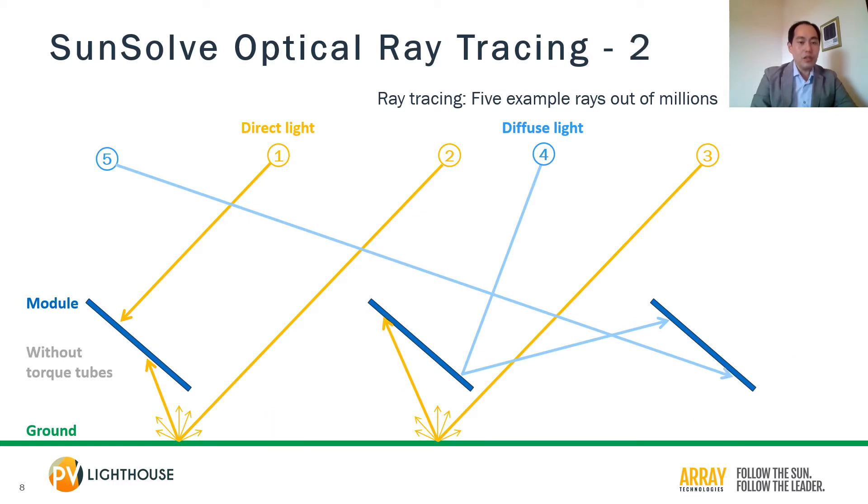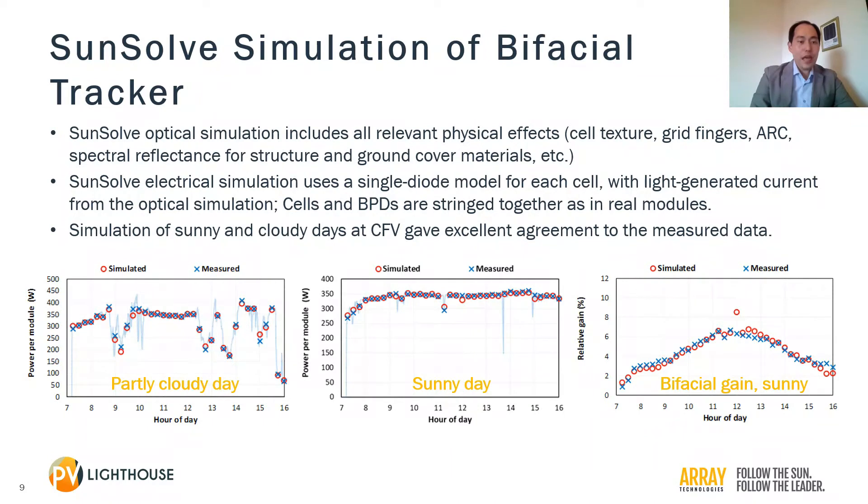As everything is virtual, we can vary the properties of each interface and medium at will to gain insight into an observed phenomenon. For example, we can turn the torque tube on and off to quantify the shading loss from the torque tube. We have an accurate estimation of the total irradiance into each cell because the SunSolve simulation includes all the relevant physical effects. We then followed through with the electrical simulation, representing each cell with a single diode model to simulate the electrical network of cells and bypass diodes as they are stringed together in real PV modules. SunSolve simulation of sunny and cloudy days at CFV gave excellent agreement to the measured data, providing validation of the SunSolve software.